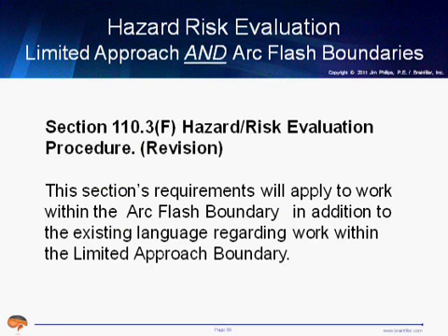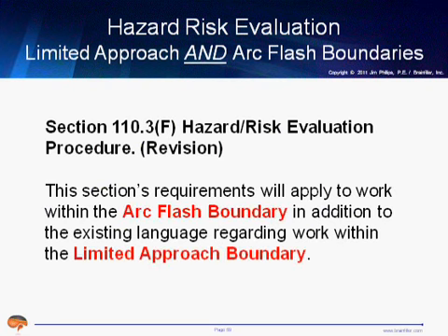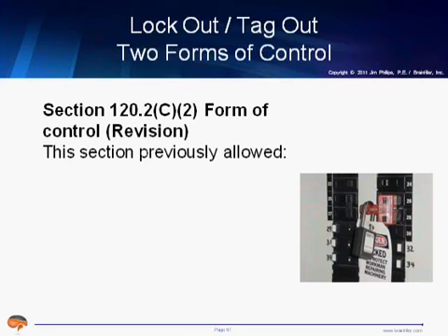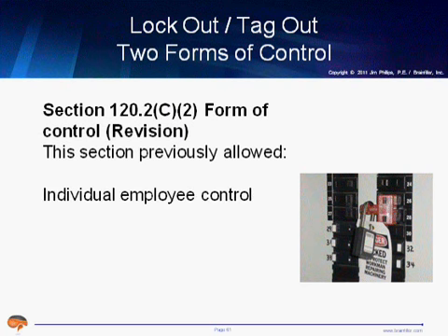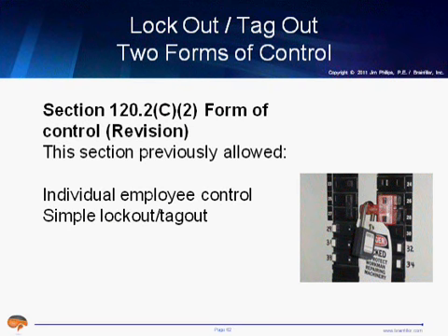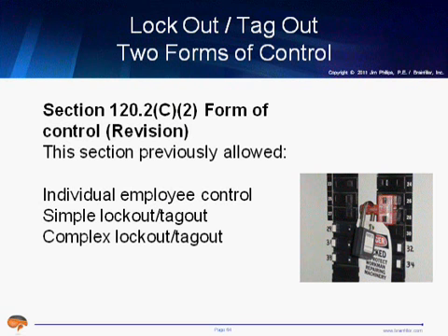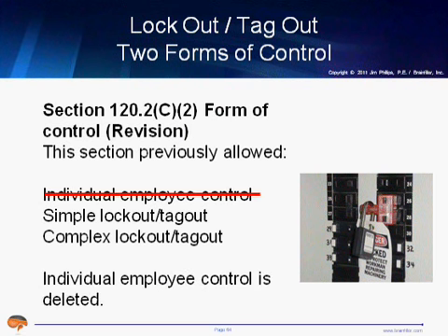The risk evaluation, there's also been a change here where this not only applies with the limited approach boundary, but the arc flash boundary has been included within this one as well. Lockout tagout has changed. Up through the 2009 edition, there were originally 3 forms of control. You can have individual employee control, and this was for minor work, or you can have a simple lockout tagout, or you can have a complex lockout tagout for shift changes and things like that. Well, beginning in 2012, the individual employee control is being eliminated. So you're left with either simple lockout tagout or complex lockout tagout.